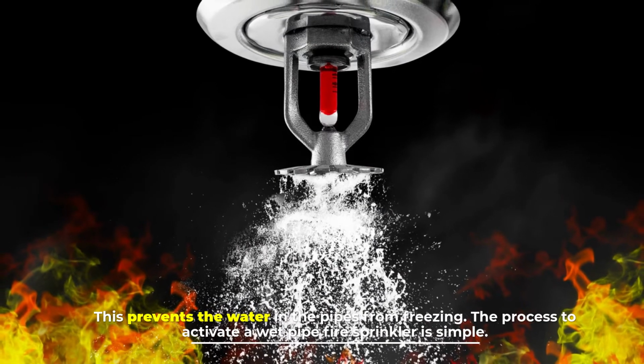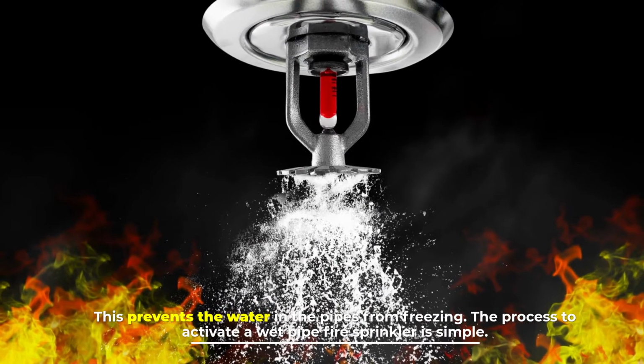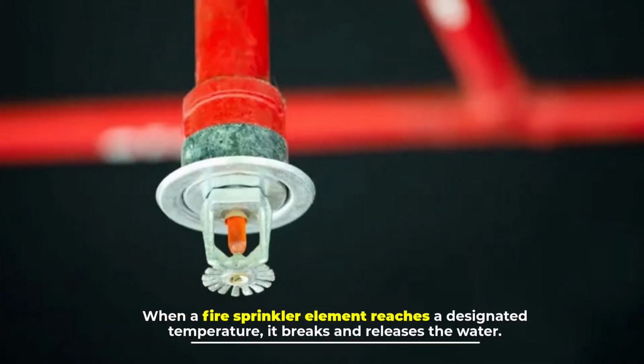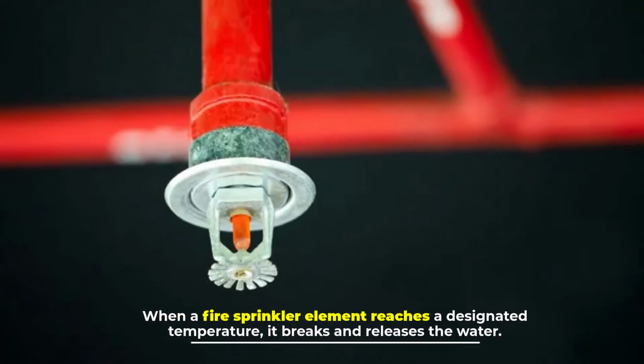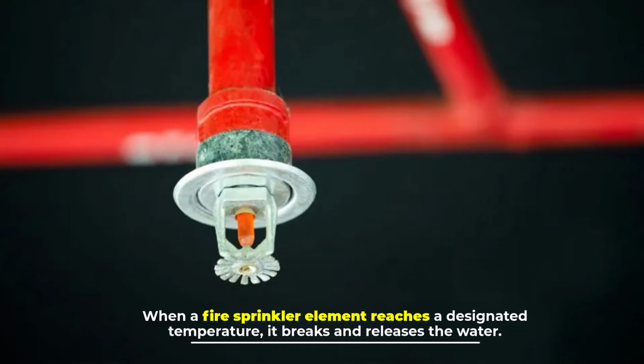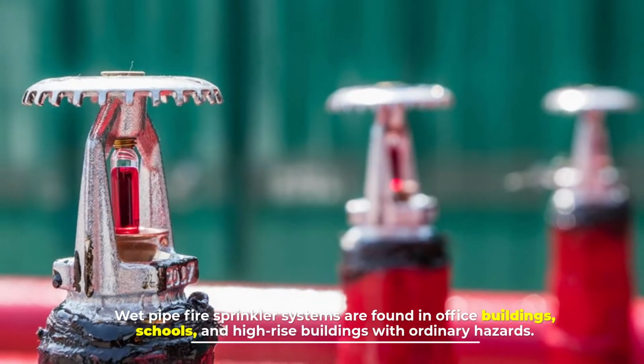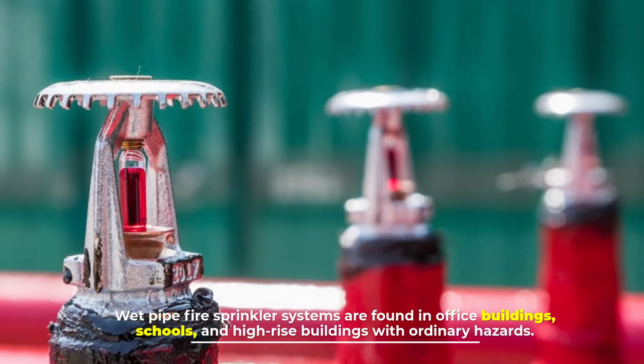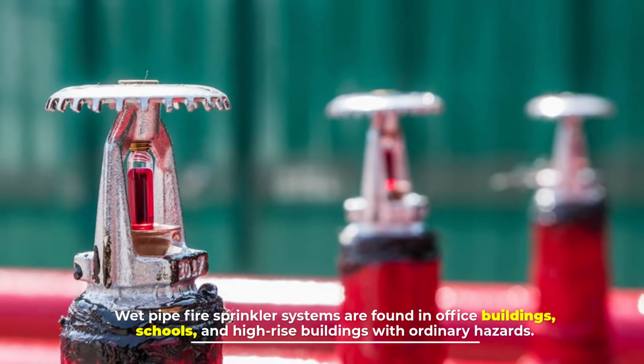The process to activate a wet pipe fire sprinkler is simple. When a fire sprinkler element reaches a designated temperature, it breaks and releases the water. Wet pipe fire sprinkler systems are found in office buildings, schools, and high-rise buildings with ordinary hazards.